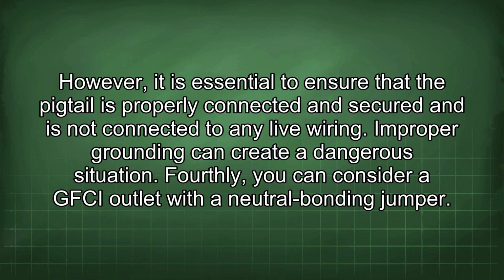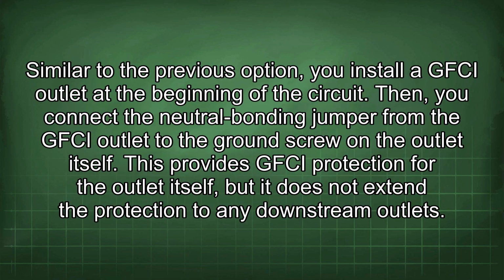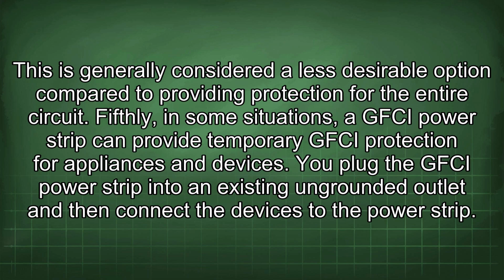Fourthly, you can consider a GFCI outlet with a neutral bonding jumper. Similar to the previous option, you install a GFCI outlet at the beginning of the circuit. Then, you connect the neutral bonding jumper from the GFCI outlet to the ground screw on the outlet itself. This provides GFCI protection for the outlet itself, but it does not extend the protection to any downstream outlets. This is generally considered a less desirable option compared to providing protection for the entire circuit.